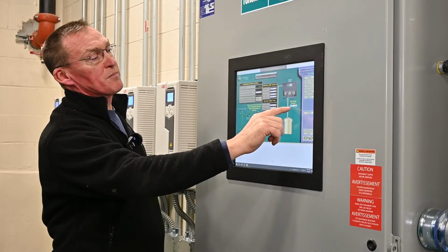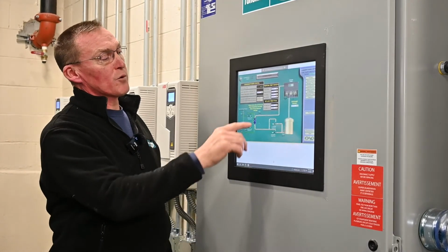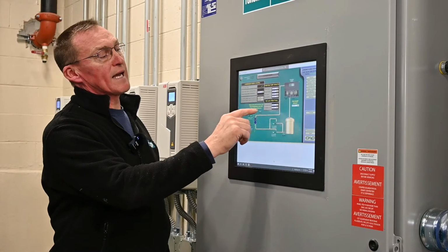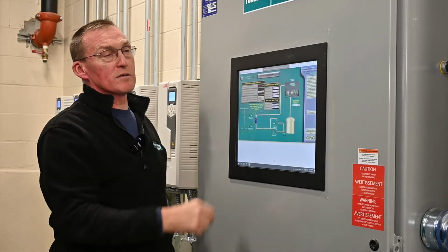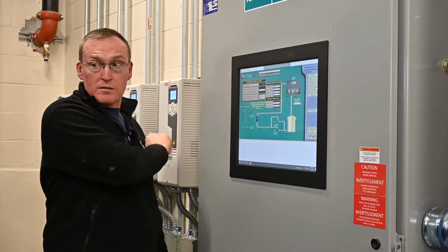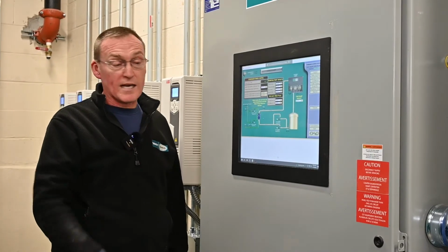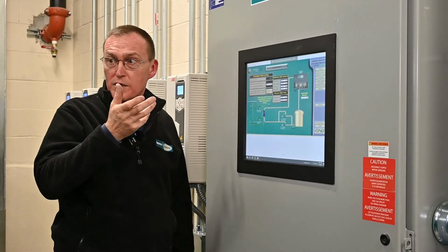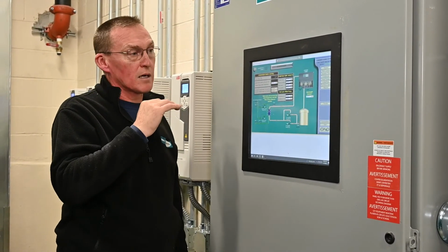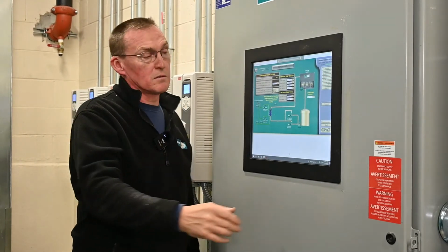And then fan ramp target. That's set for 94 degrees. That looks at this temperature right here. That is what tells this fan to tell this VFD to start speeding up. And it's not going to go up and down, go crazy. It's going to go very slowly, and it's going to maintain a constant, consistent level.